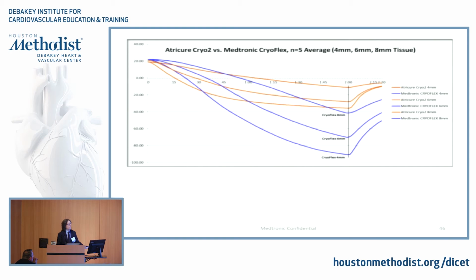Why is it important? It's important because we have to modify the duration of the freezing. The problem is that we cannot predict it when we are in the OR, but we need to be aware of it. So what happens if you increase the cryo to 3 minutes? I tell you, it may be working well, but it may be not working well. And we are showing in the paper that actually the algorithm of cooling tissue is different between the two devices. And the longer is not necessarily better when it comes to this device.